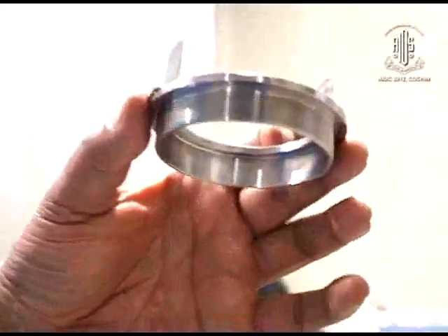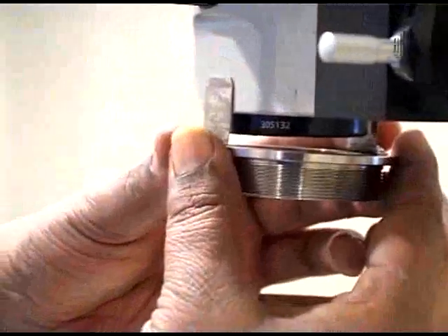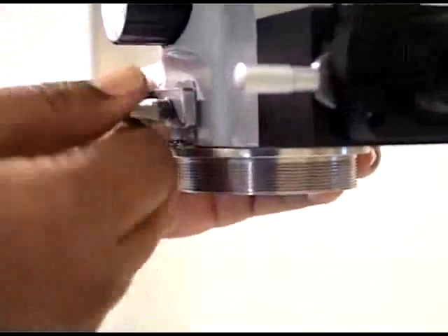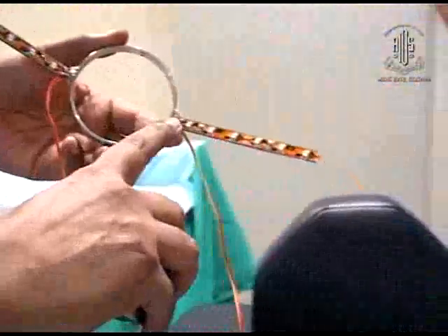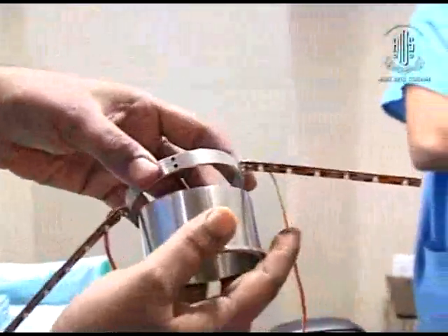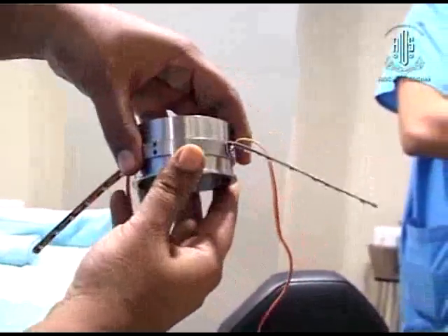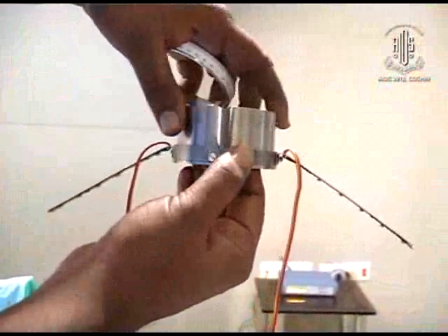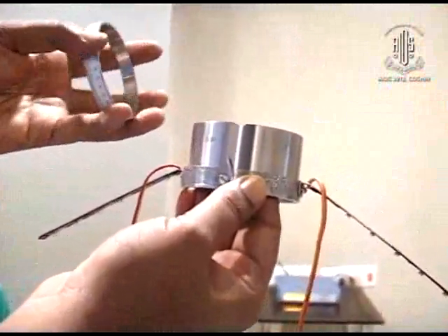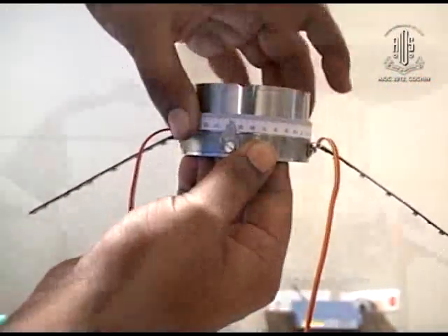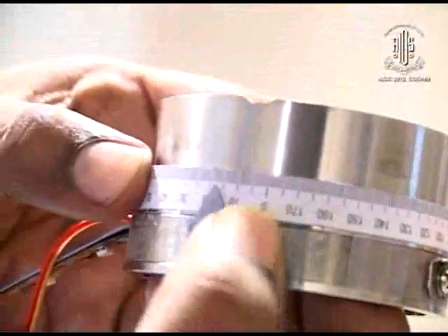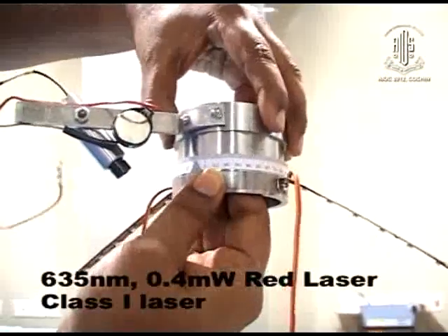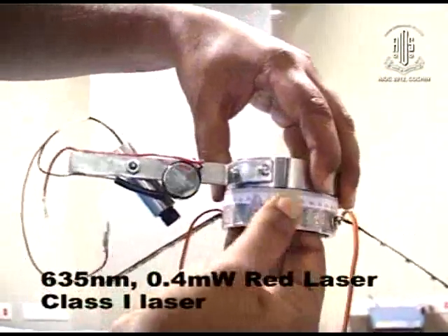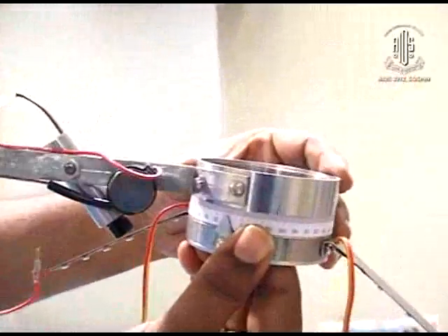It comprises a holding ring that bears the weight of the device and is secured in place with the help of a C-clamp such that it does not fall off inadvertently. The lower ring has 2 wings about 4 inches in length, which hold a row of 6 LED lights on each side. This ring has a pointer over there. The middle ring has a graduated scale from 0 degree to 180 degree and again back to 0 degree with 1 degree steps. The upper ring holds a medical grade line laser light with an output power of less than 0.5 milliwatts. Now you see the whole device is ready.